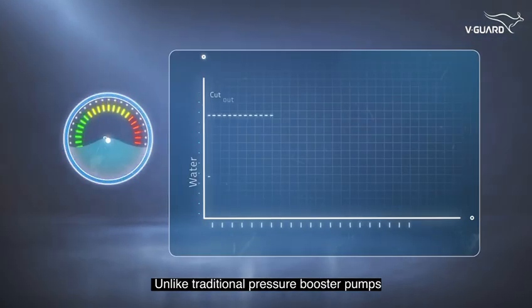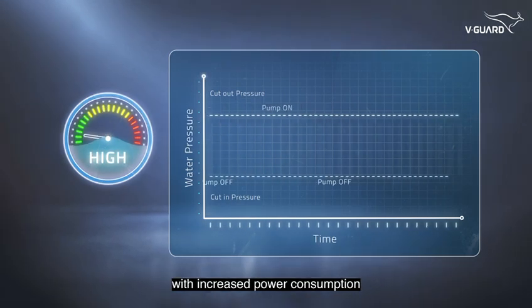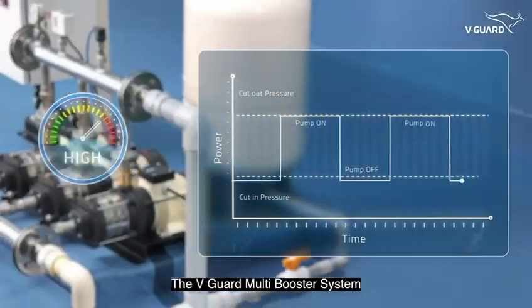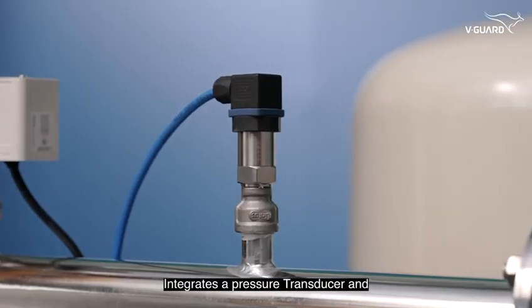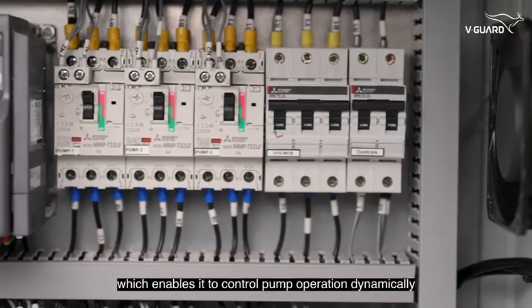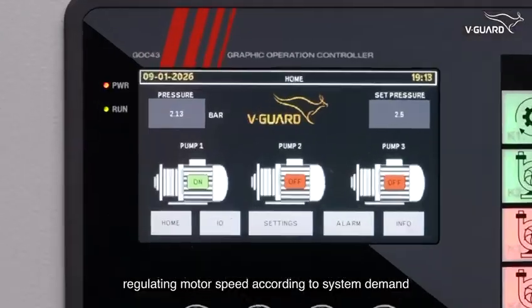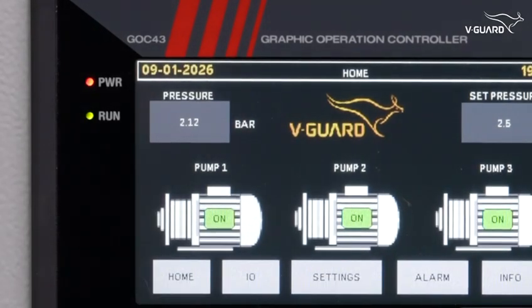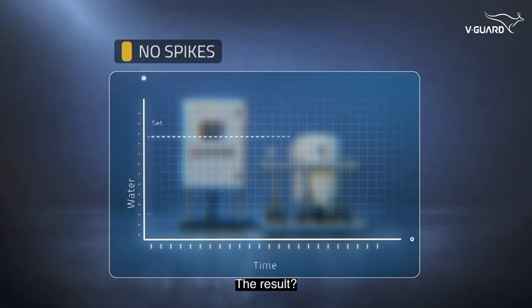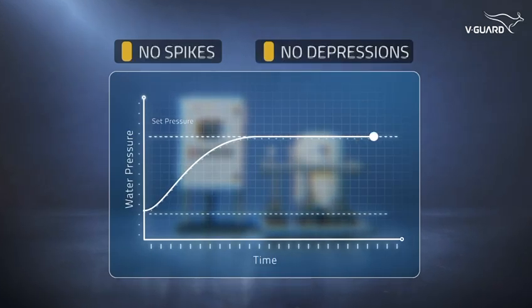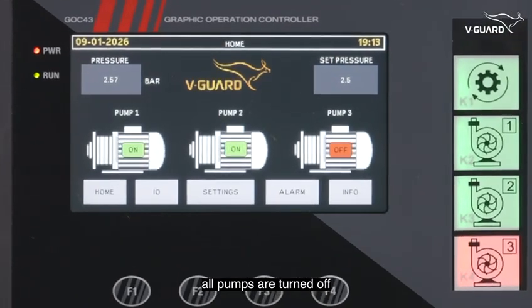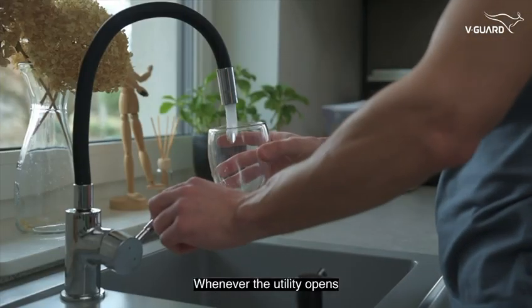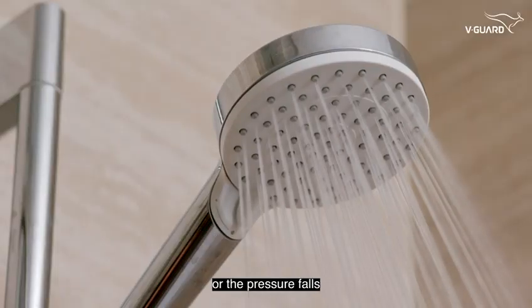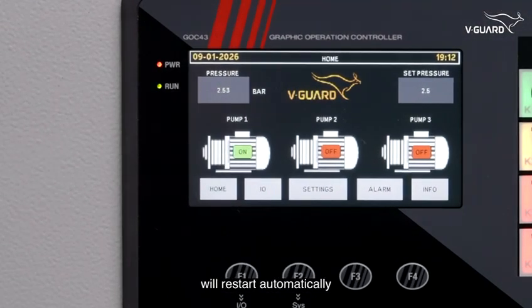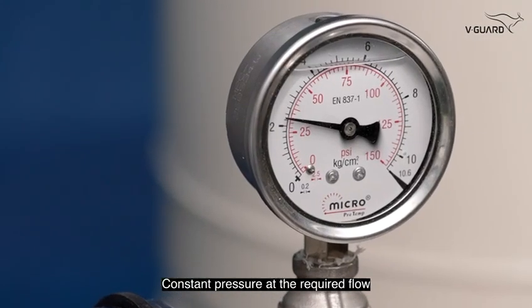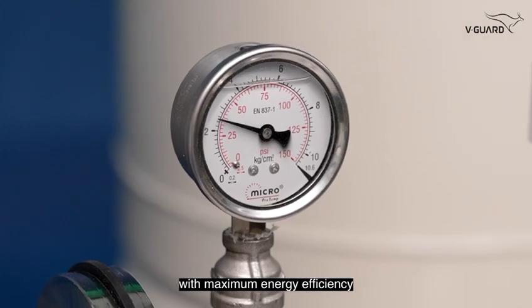Unlike traditional pressure booster pumps that operate continuously at full speed with increased power consumption, the V-Guard Multi-Booster System integrates a pressure transducer and a variable frequency drive, which enables it to control pump operation dynamically, regulating motor speed according to system demand. The result? No spikes, no depressions. If there is no demand, all pumps are turned off. Whenever the utility opens, demand resumes, or the pressure falls, the V-Guard Multi-Booster System will restart automatically. Constant pressure at the required flow with maximum energy efficiency.